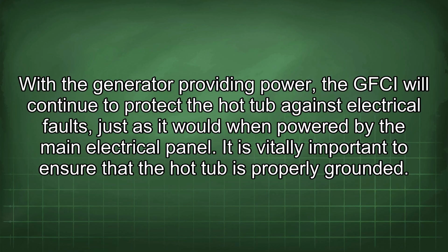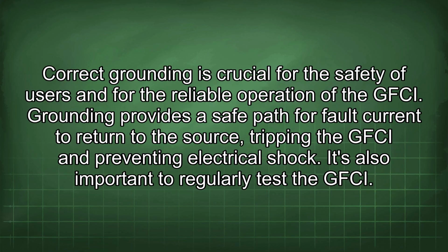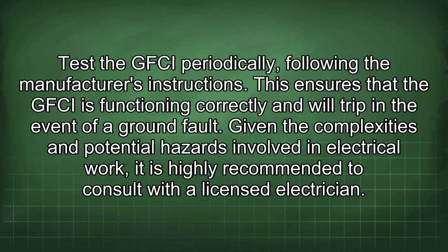It is vitally important to ensure that the hot tub is properly grounded. Correct grounding is crucial for the safety of users and for the reliable operation of the GFCI. Grounding provides a safe path for fault current to return to the source, tripping the GFCI and preventing electrical shock. It's also important to regularly test the GFCI. Test the GFCI periodically, following the manufacturer's instructions. This ensures that the GFCI is functioning correctly and will trip in the event of a ground fault.